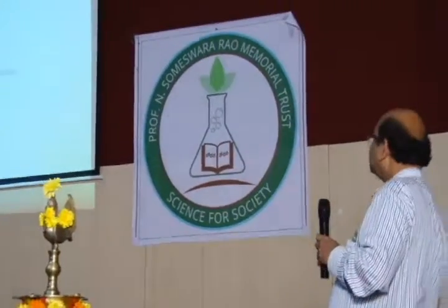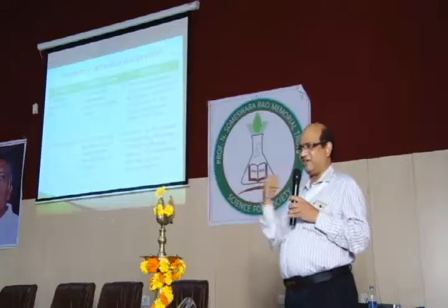Some problems I have given many times. In activated sludge plants, sludge bulking takes place sometimes because of excess MLSS. The total tank will be filled with sludge, and sludge floating will be there, especially when filamentous organisms are present. Everything will float, and the solutions I have given.